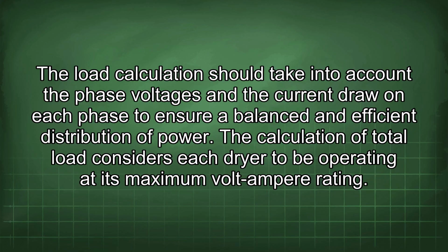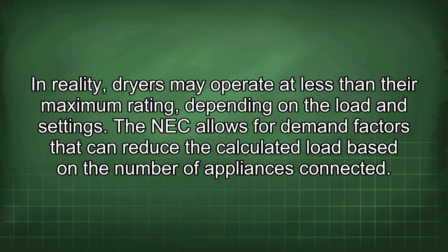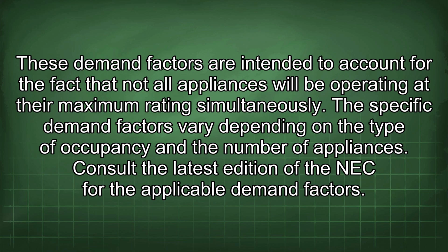The calculation of total load considers each dryer to be operating at its maximum volt-ampere rating. In reality, dryers may operate at less than their maximum rating depending on the load and settings. The NEC allows for demand factors that can reduce the calculated load based on the number of appliances connected. These demand factors are intended to account for the fact that not all appliances will be operating at their maximum rating simultaneously. The specific demand factors vary depending on the type of occupancy and the number of appliances. Consult the latest edition of the NEC for the applicable demand factors.